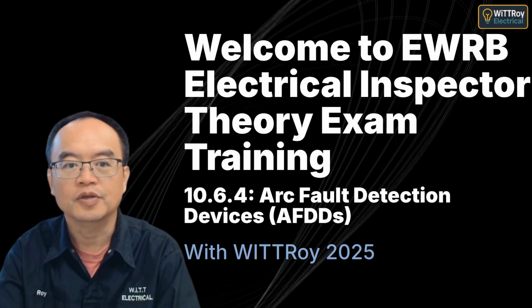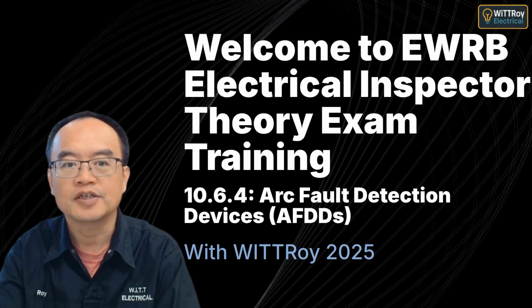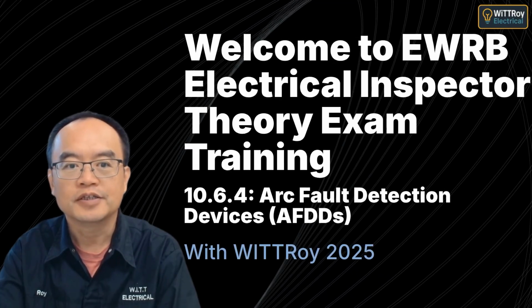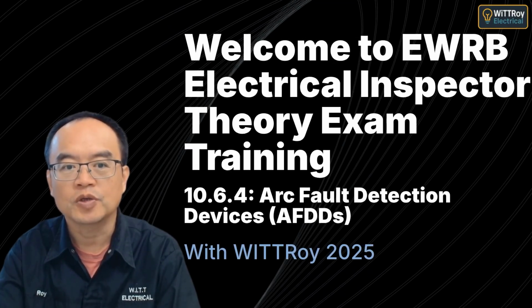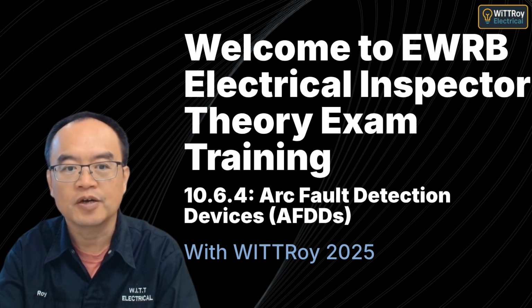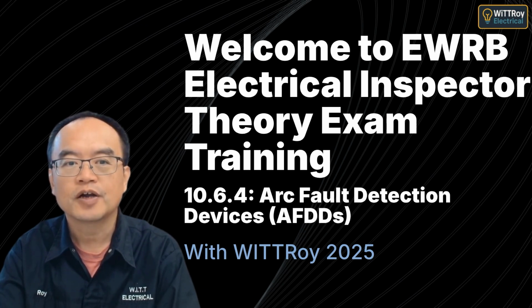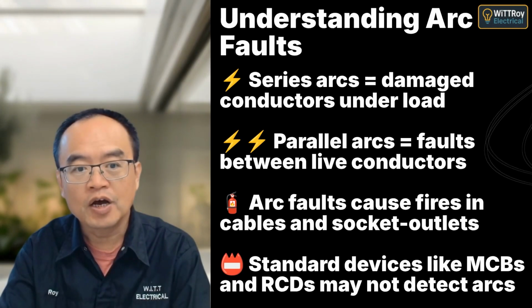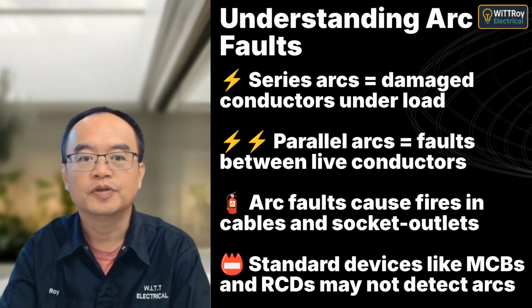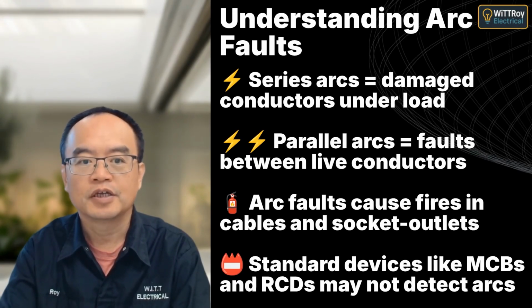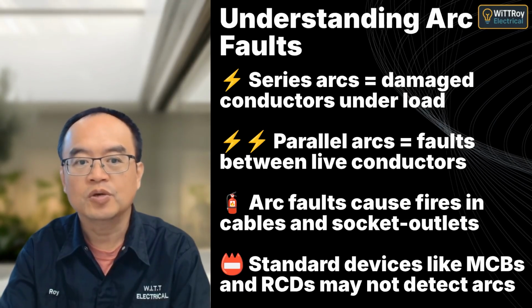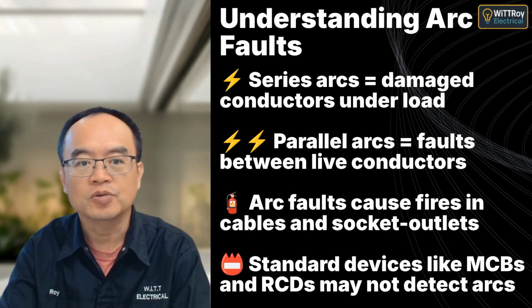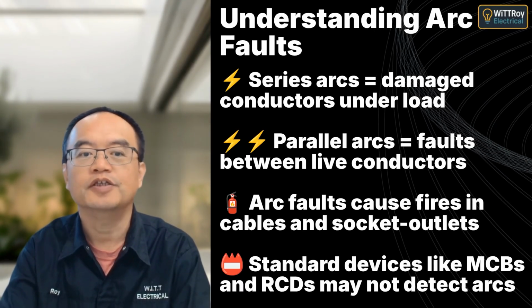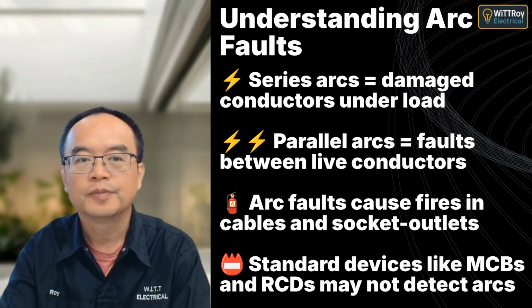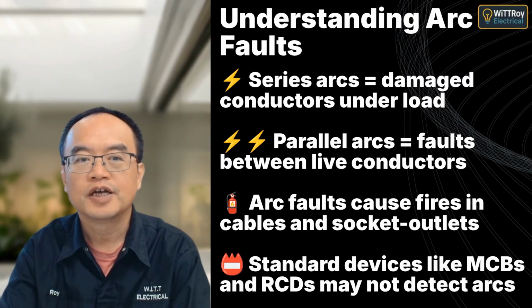In this short lesson, we're focusing on arc fault detection devices, or AFDDs, how they work, the risks of arc faults, and why these devices are valuable in protecting final subcircuits from electrical fires. Arc faults are dangerous and often caused by damaged cables or poor terminal connections. Series arcs happen within a single conductor, while parallel arcs occur between conductors. Standard protection like RCDs or MCBs may miss these faults. This is where AFDDs come in.